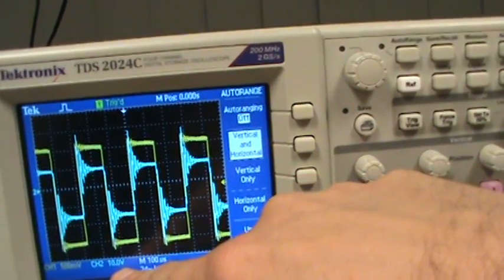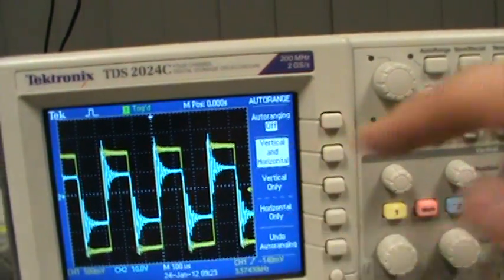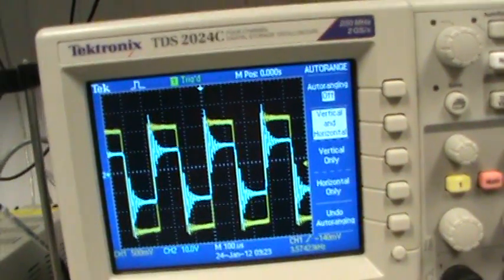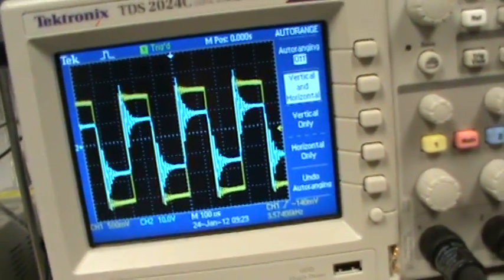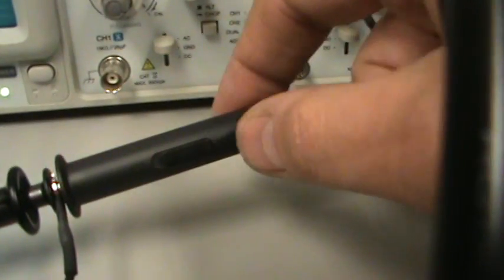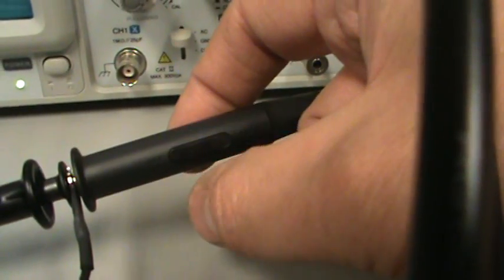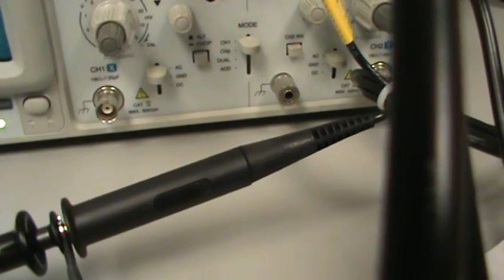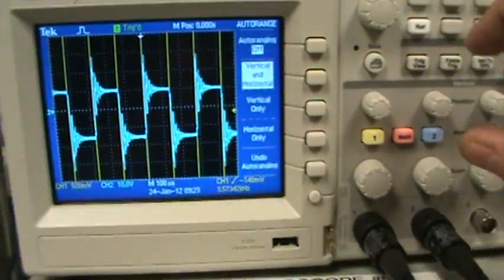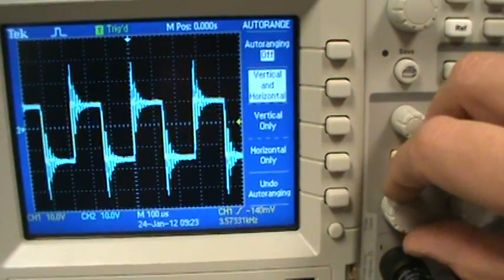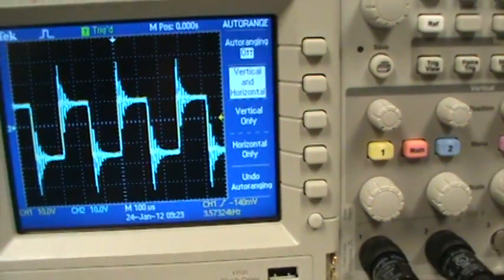And so channel 2 is 10 volts, channel 1 is 500 millivolts. And the reason we have the difference is on the probe. So if you look down here on the probe, there's a switch here, 10 times probe and 1 times probe. You want to make sure that the probe setting on the oscilloscope is the same as the probe. So now this probe is at 1. And then on the oscilloscope, now the oscilloscope is set to 1.